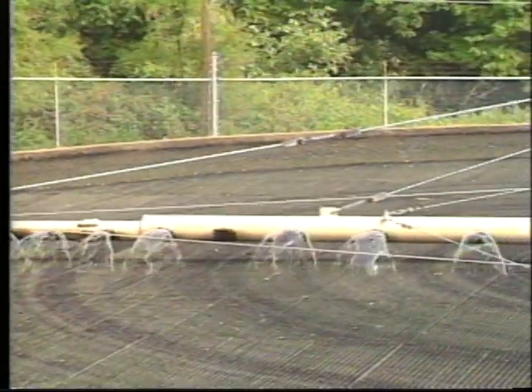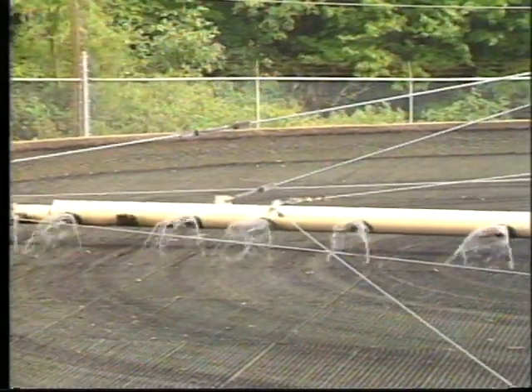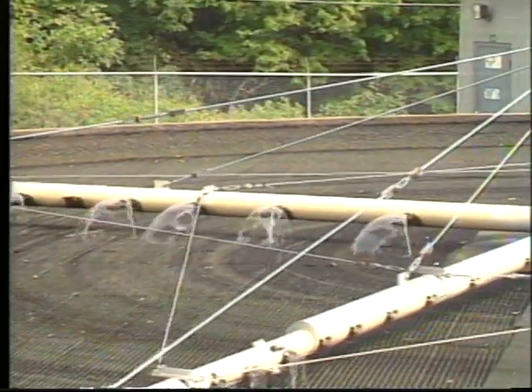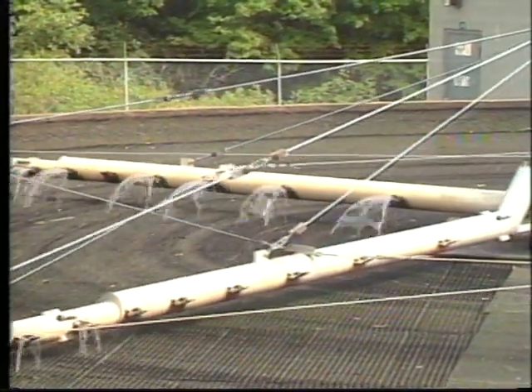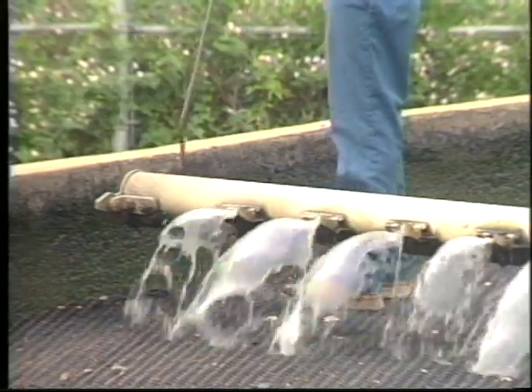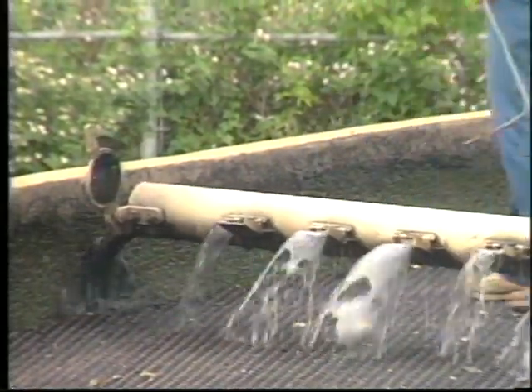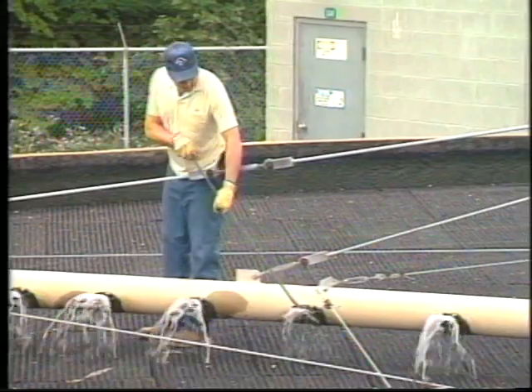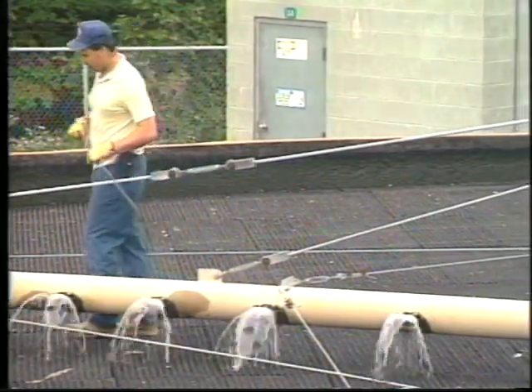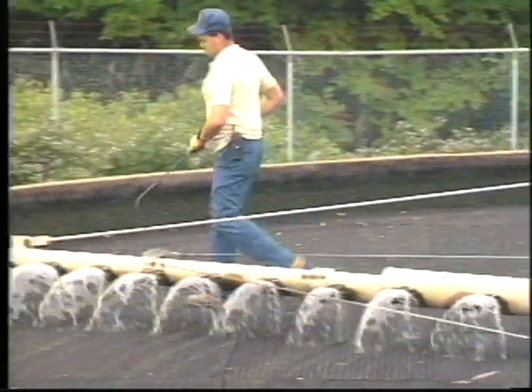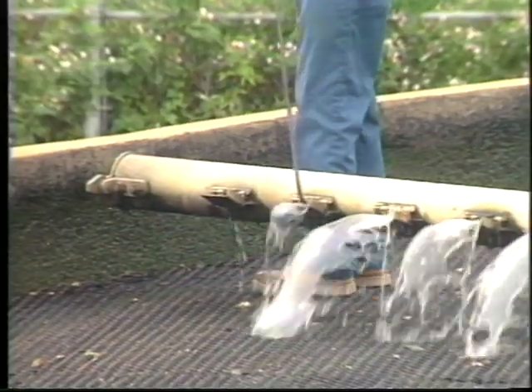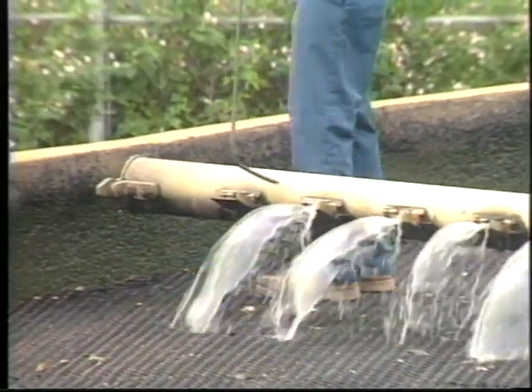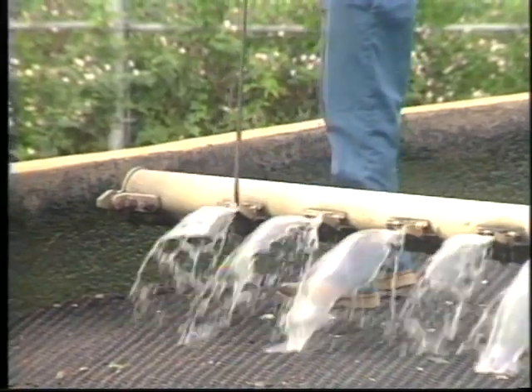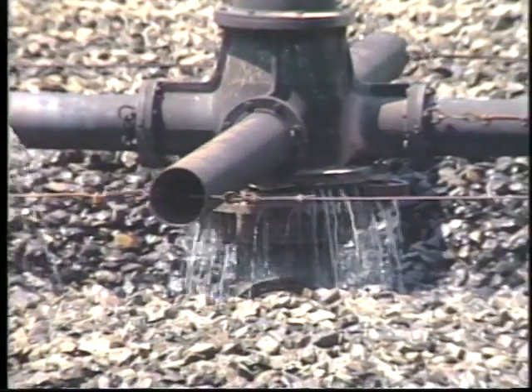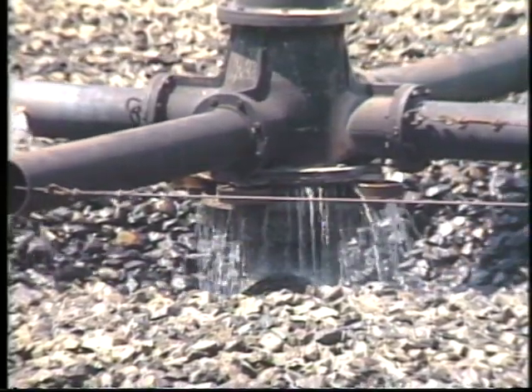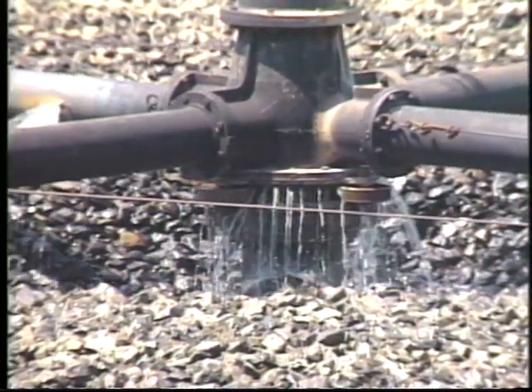In some cases, there may be orifices on the reverse side of the arm to act as reverse thrusters to control distributor arm speed. Most distributor arms have end plates that can be lifted to flush out debris. It is important to keep the flow through the distributor arm unrestricted. Keeping the orifices clean is important for proper operation of the trickling filter in both fixed and rotating distribution systems. In the center column of the rotating distributor, you will find bearings and seals that must be maintained.